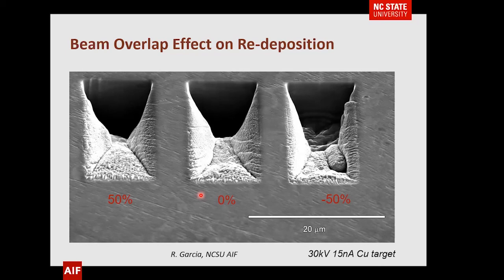Q&A: Can FIB be adapted to work with other than gallium source? Yes. People have used a number of sources — indium is frequently an option. What has come about more recently are the new gas sources: plasma FIBs, where instead of maybe 30 nanoamp beams, they're up to 2 or 3 microamps with a sputtering rate more than 100 times faster. People also do ion implantation using a multi-element source with a mass spectrometer to filter and implant — for example, silicon into a material — making discrete devices that are radiation-hardened. But most of what you're going to see commercially are gallium sources. Gold and bismuth are also used as sources, seen on instruments such as the time-of-flight mass spectrometer.